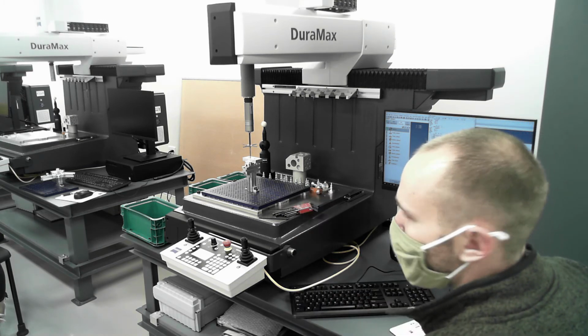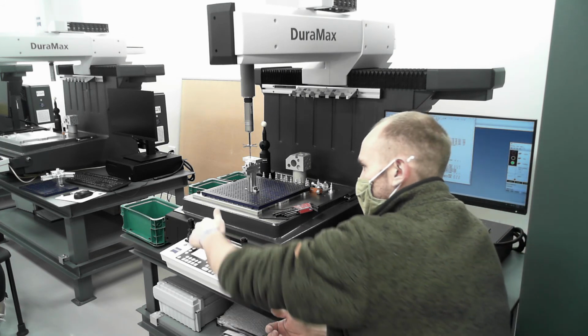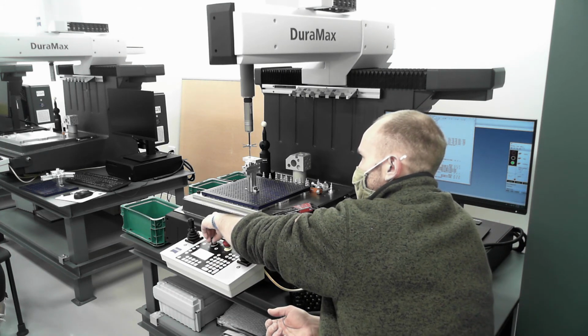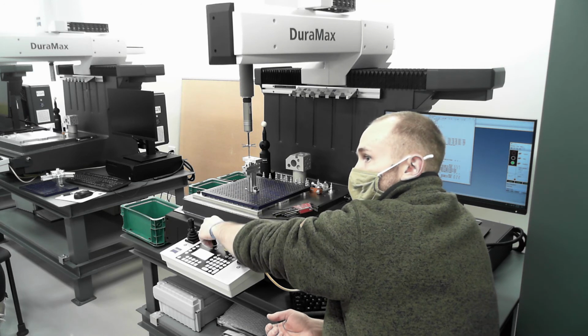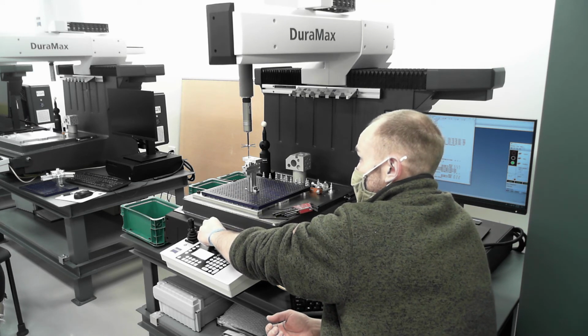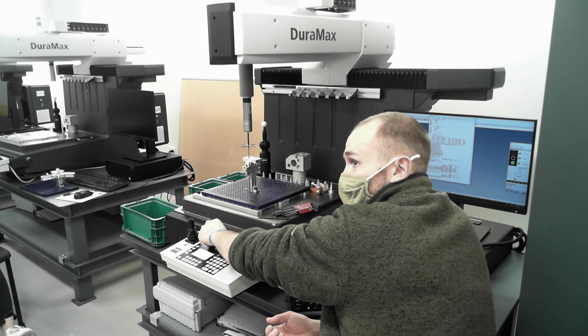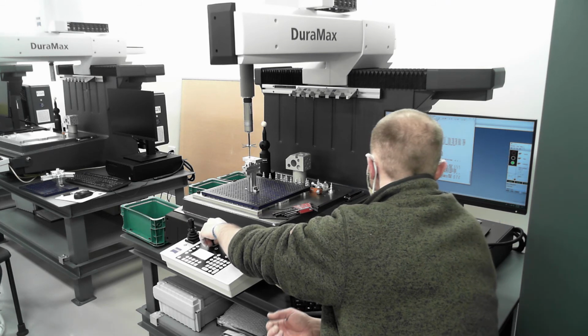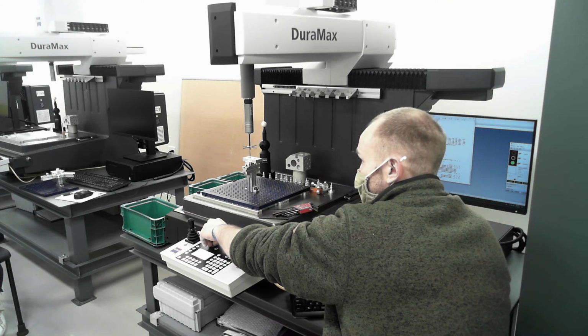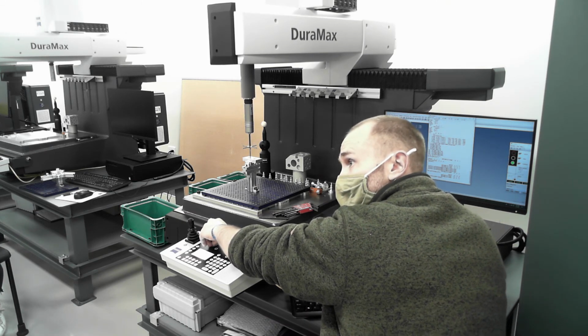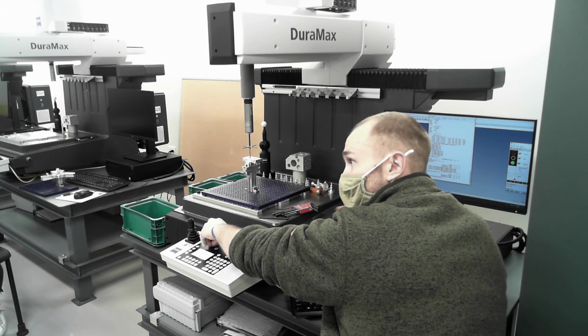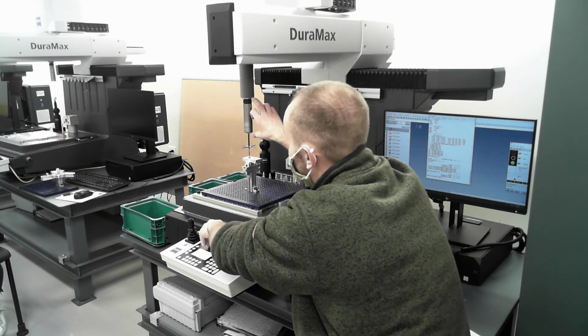See how painfully slow the scan path is when you're running the speed dial at anything other than full speed? You're also influencing the results of your measurement by running this at anything other than full speed. So it will be slow going when you run in step mode, but the cost of skipping step mode can be huge, right? Again, 15 grand right there.